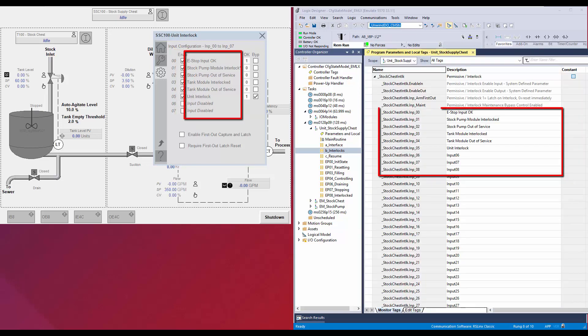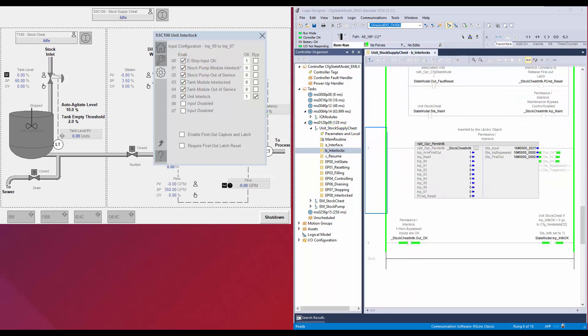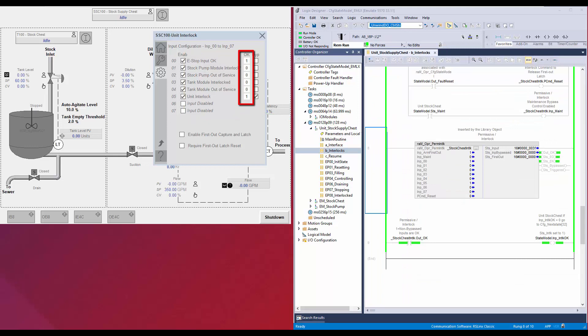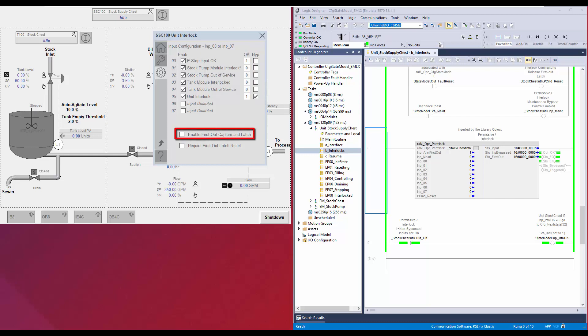In the configuration tab, these checkboxes are to enable or disable an input. The input description can be modified from the logic designer. This is the OK state for the inputs — select as 1 or 0. This checkbox is to select if the input is allowed to be bypassed in the settings tab during maintenance. Select this option to enable the first out capture, and select this option if the first out capture is to be reset only using the reset command.